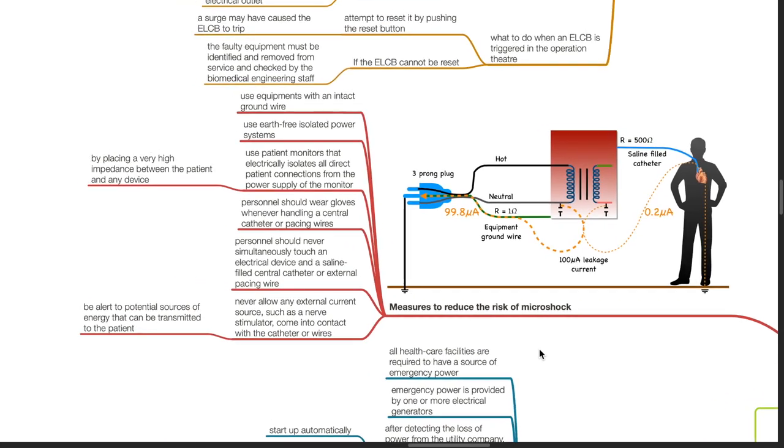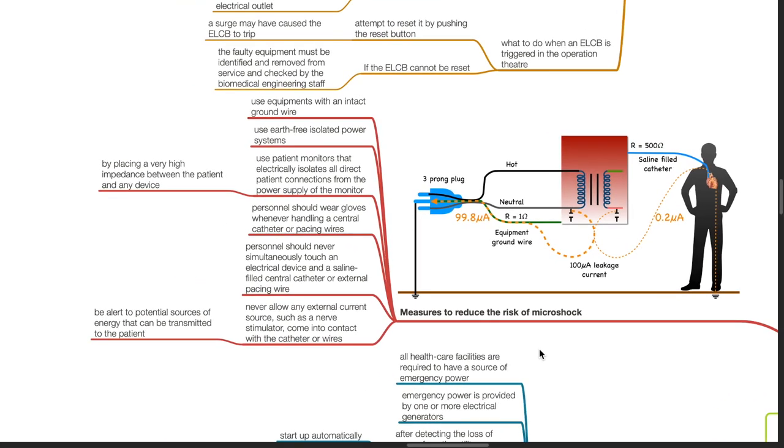Measures to reduce the risk of microshock: Use equipment with an intact ground wire. Use earth-free isolated power systems. Use patient monitors that electrically isolate all direct patient connections from the power supply by placing a very high impedance between the patient and any device. Personnel should wear gloves whenever handling a central catheter or pacing wires. Personnel should never simultaneously touch an electrical device and a saline-filled central catheter or external pacing wire. Never allow any external current source, such as a nerve stimulator, to come into contact with the catheter or wires. Be alert to potential sources of energy that can be transmitted to the patient.